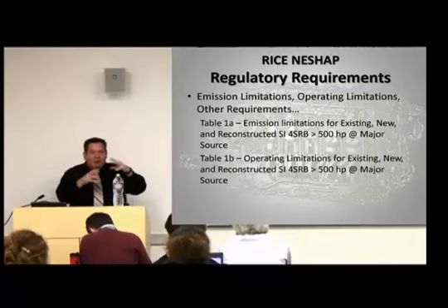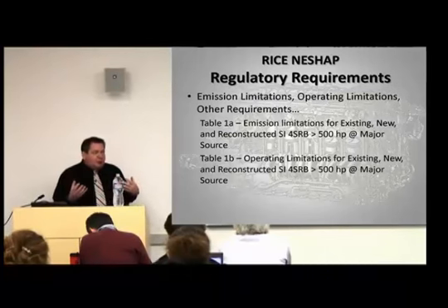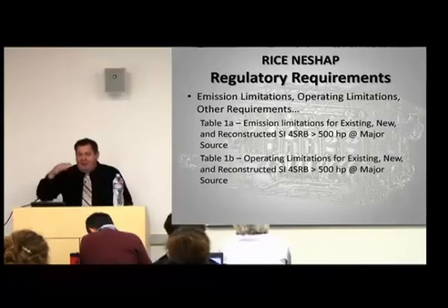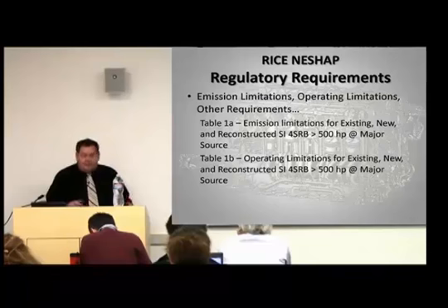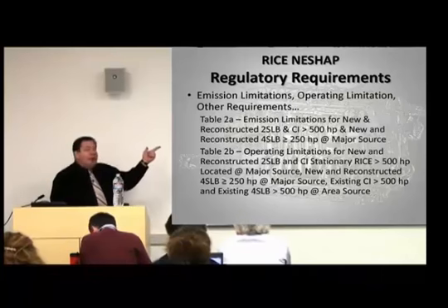So there is a little method to their madness in terms of grouping these engines, because 4-stroke rich burn engines are unique in that they have very low amounts of oxygen coming out their stack. That being the case, 4-stroke rich burn engines that need to use a catalyst will likely use a non-selective catalyst, a 3-way catalyst, as opposed to lean burn engines.